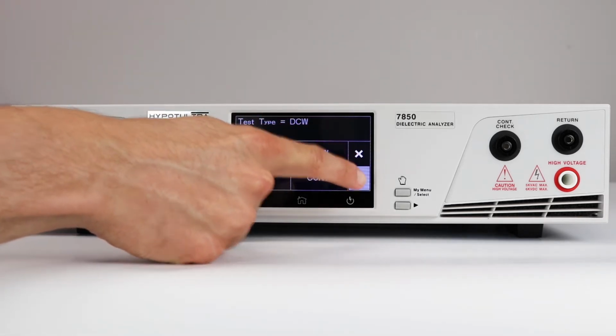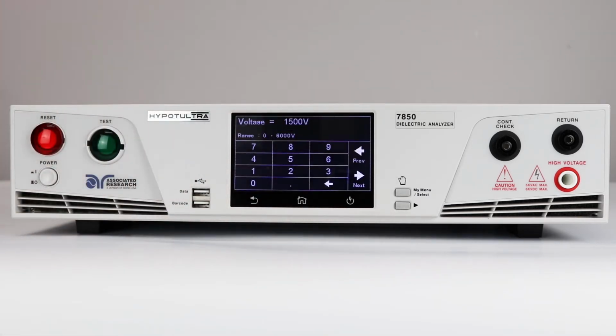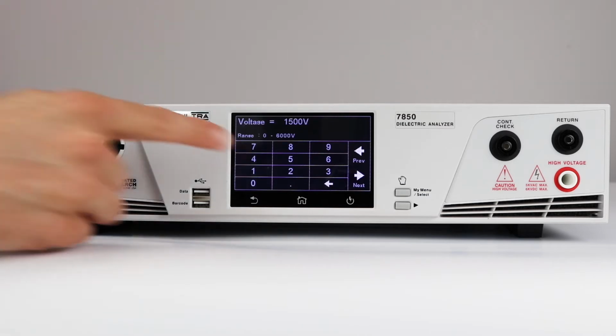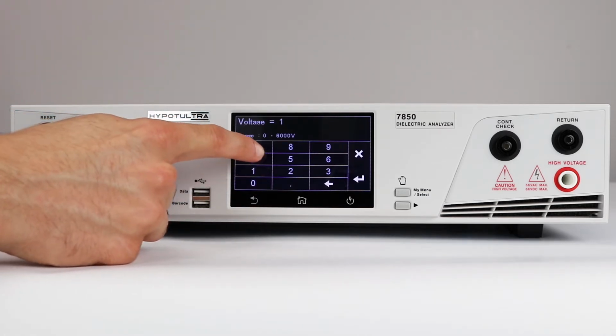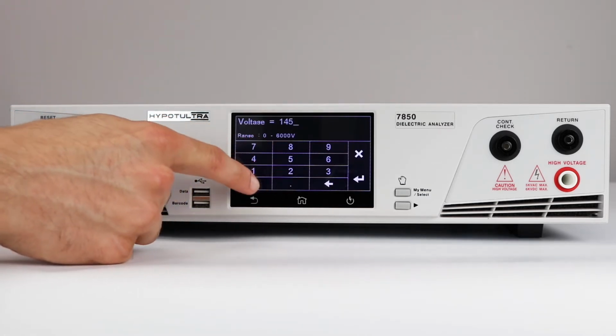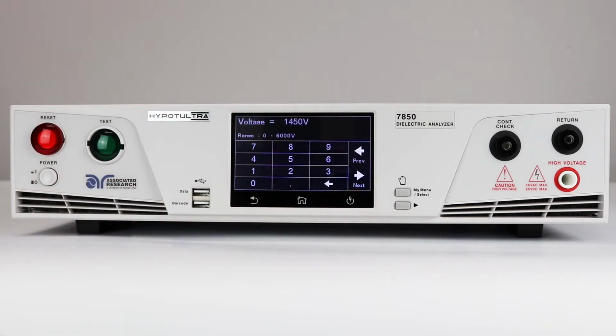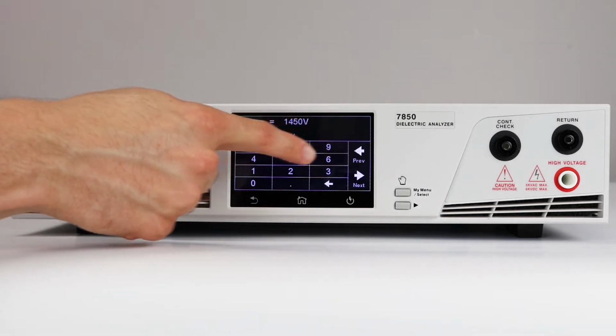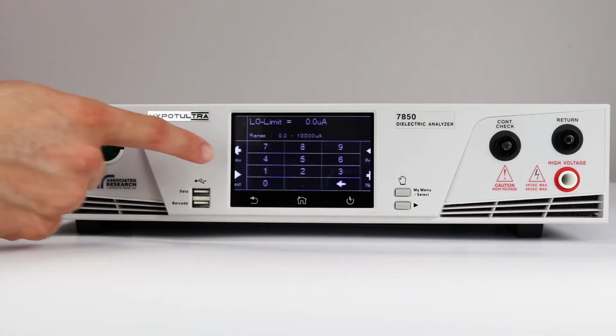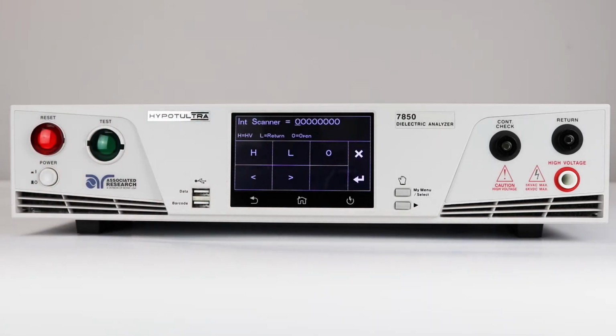Press Enter to confirm. To change the test voltage, input the numeric value on the touchscreen and touch the Enter key to confirm. To navigate between test parameters, either input the value and press the Enter key or swipe left and right to change parameters. Eventually, you will get to the internal scanner parameter. The internal scanner is optional hardware on the HypotULTRA.